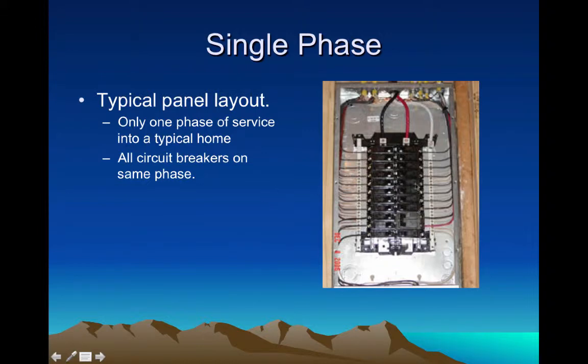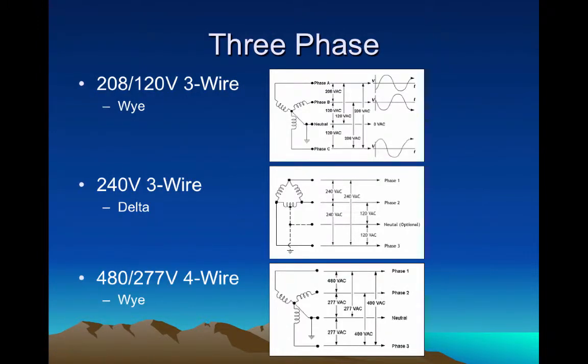In the end, all those circuits are on the same phase. When we get into three-phase systems in larger commercial and industrial facilities, there are a couple of different configurations: 208/120 volt, 240 volt three-wire, or 480/277 volt. A lot of these will depend on the application — some high-powered lighting systems for auditoriums may require 277 volt, or certain machinery may require 240 volt. It really depends on the facility, and there could be different types at different points within the facility.